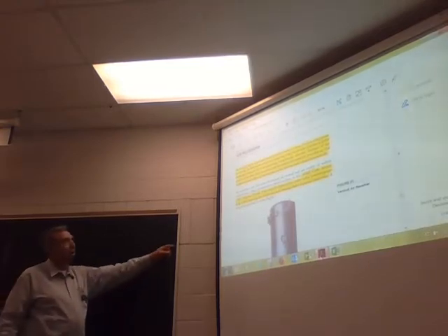All right? Air receivers. This is important. Did I mention this is important? Okay, just in case you wonder. An air receiver is a pressure vessel. Remember that. It's controlled by ASME, right? A pressure vessel which is used as a reservoir in a compressed air system. In addition to acting as a reservoir, it acts to dampen pulsations in the discharge pressure of a reciprocating compressor.